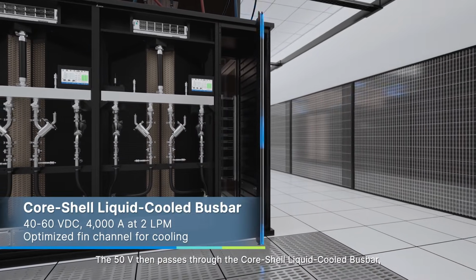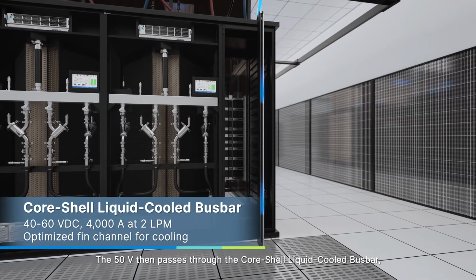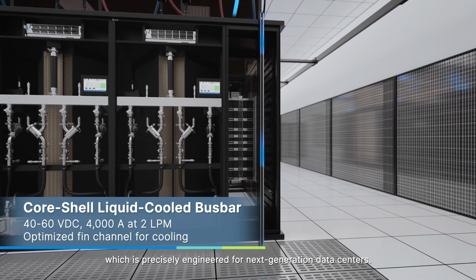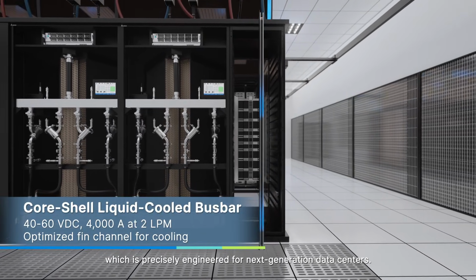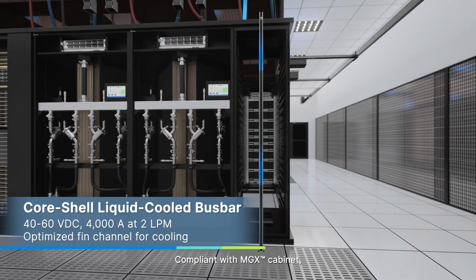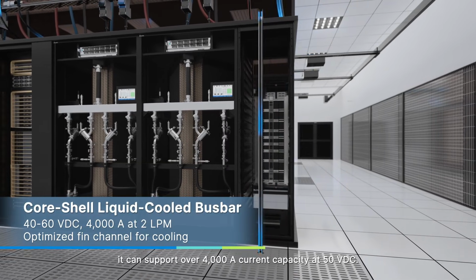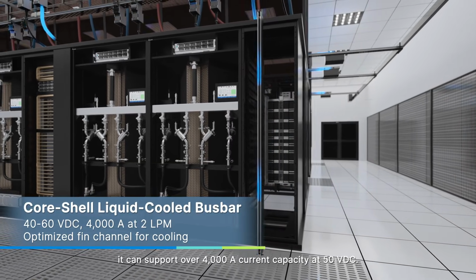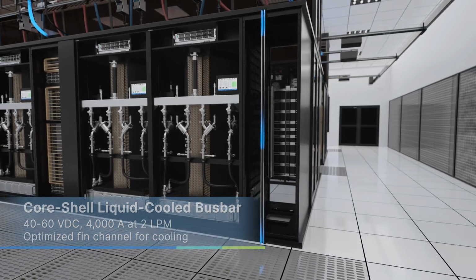The 50 volts then passes through the core shell liquid-cooled busbar, which is precisely engineered for next-generation data centers. Compliant with MGX cabinet, it can support over 4,000 amps current capacity at 50 volts DC.